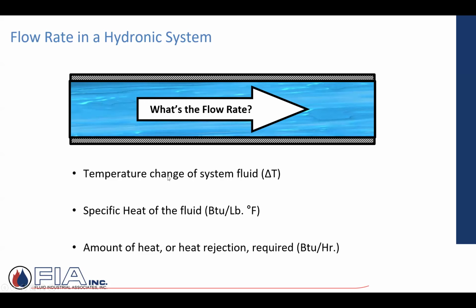So in this case, they're talking about a change in temperature. It's a sensible temperature that we're measuring. So it's water. It's not a gas. It's not steam. It's water. It's going to stay water. It's just going to change in temperature. Specific heat of the fluid, typically what we're dealing with for the most part is going to be water. There are instances and examples where maybe we're not, and that specific heat may change, which can influence the formula, the calculation. And then the last part here is, okay, what's the load? Are we trying to heat something or are we trying to cool something? Are we removing heat or are we providing heat? What's the BTU load?